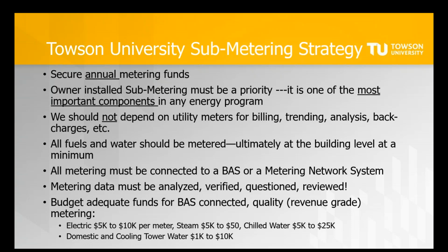So a couple of bullet points here. Owner-installed submetering must be a priority. It's one of the most important components in any energy program, as mentioned earlier. We should not depend on utility meters for billing, trending, analysis, or back charges. We like to think of utility metering as supplemental metering. All fuels and water should be metered, ultimately at the building level at a minimum.